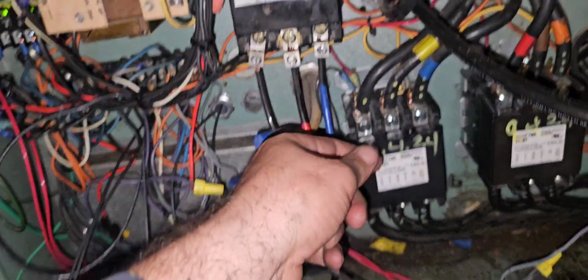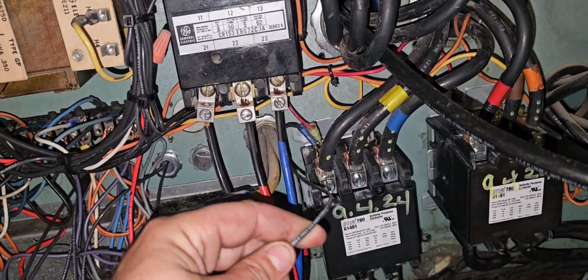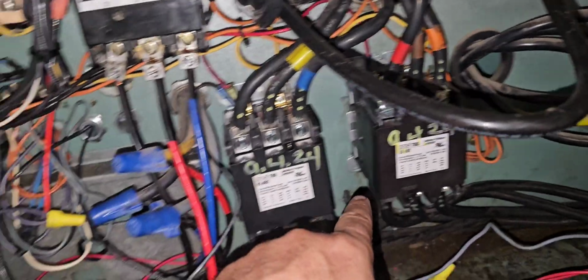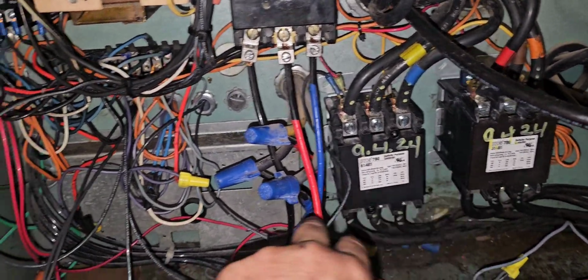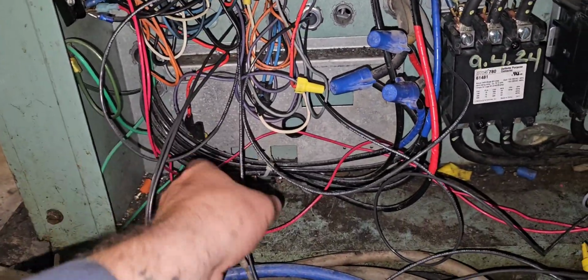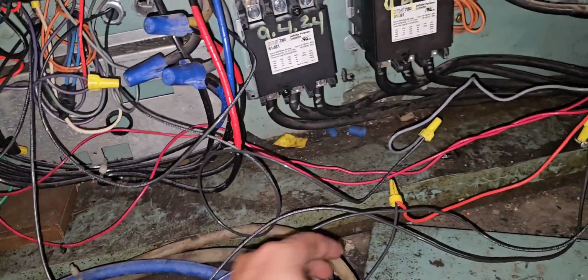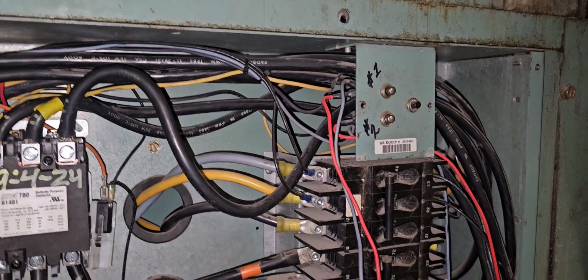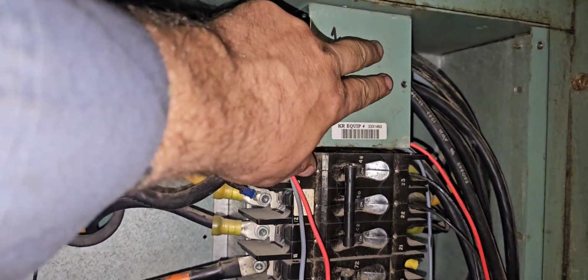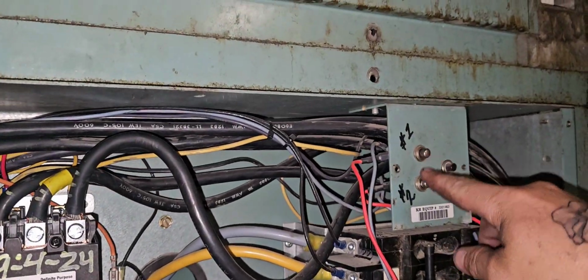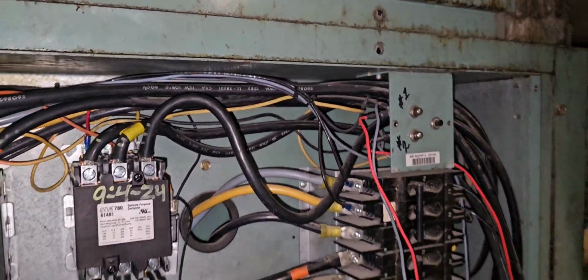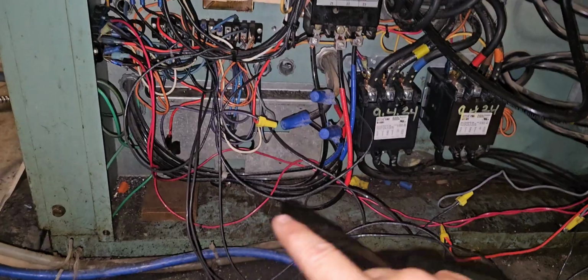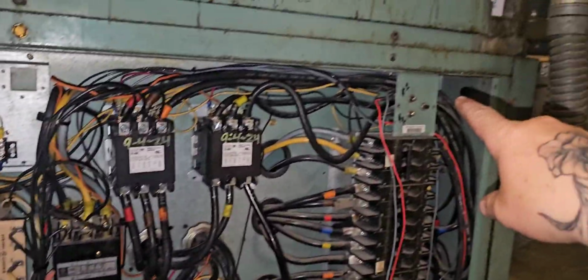So I have one side that's going to my contactor, and then that is being jumped over to this contactor. These are split winding compressors, so I have two contactors. And then I have the other side that's going up to my fuses. These are my fuses right here: compressor one, compressor two, and my air handler. I have those wires tied in to my contactor and then to my fuses, right? So that's how that's wired up.